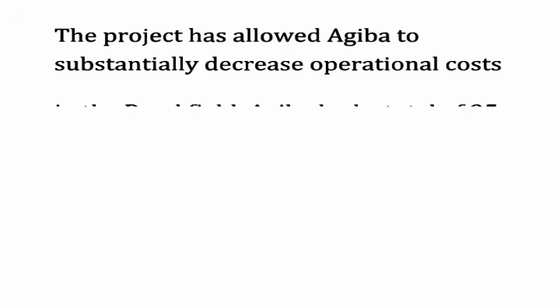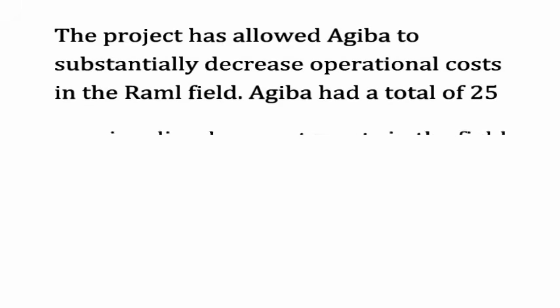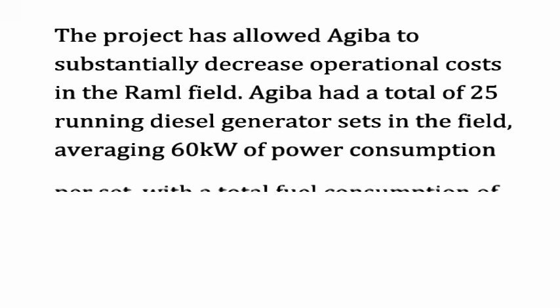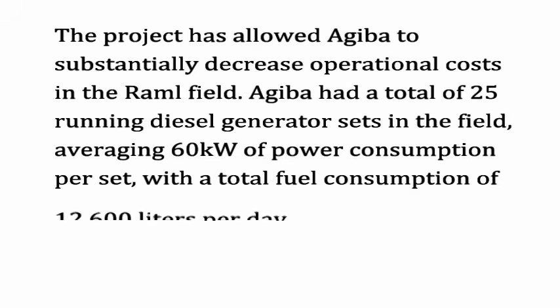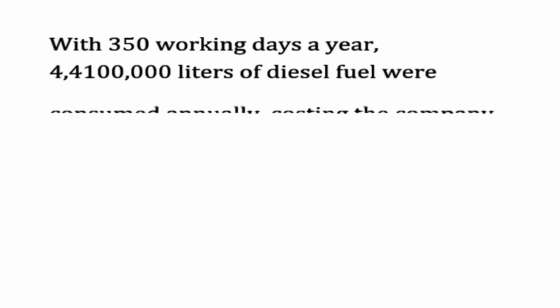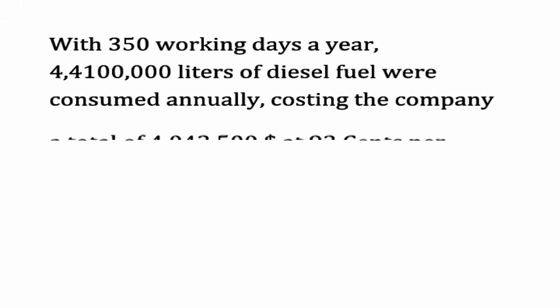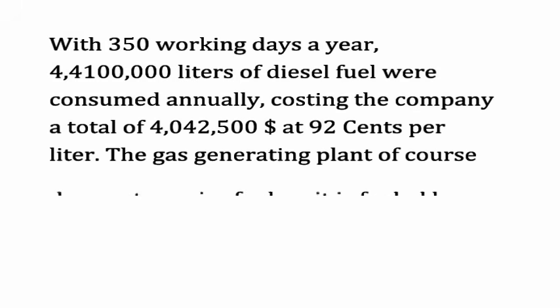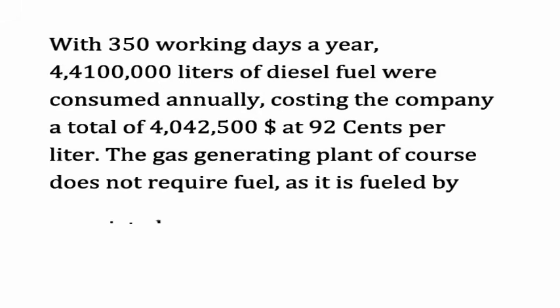The project allowed Agiba to substantially decrease operational costs in the Raml field. Agiba had a total of 25 running diesel generator sets in the field, averaging 60 kilowatts of power consumption per set, with a total fuel consumption of 12,600 liters per day. With 350 working days a year, 4,410,000 liters of diesel fuel were consumed annually, costing the company a total of $4,042,500 at $0.92 per liter. The gas generating plant does not require fuel as it is fueled by associated gas.